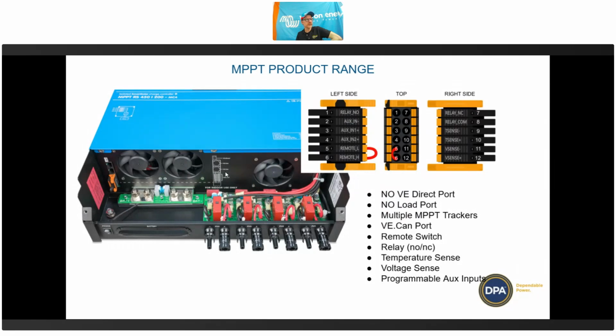So the largest that they make is the RS range, with a 450 volt input. They make a 100 amp and a 200 amp version of that. It's pretty similar, but it just looks quite different. Again, it doesn't have a VE.Direct port. It only has VE.Can. It doesn't have a load port. It has multiple MPPT trackers in it, so multiple channels, so you can put different strings of different voltages into those channels. It has a remote switch, a relay, and voltage and temperature sensing. There's not a lot more to say about that one other than that this has built-in earth guard protection as well. So you don't need to put in, say, an earth guard with these because they have that built in, whereas with the rest of them, if you're over the voltage threshold, then you need to put in an earth guard of some description with the smaller size ones.